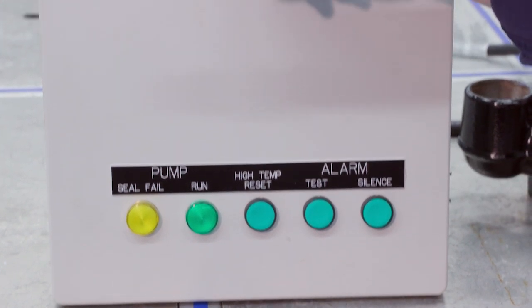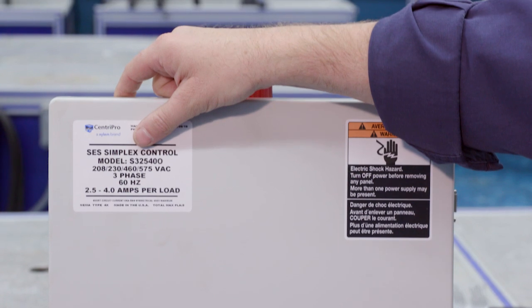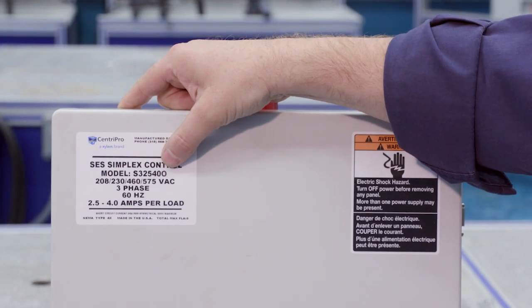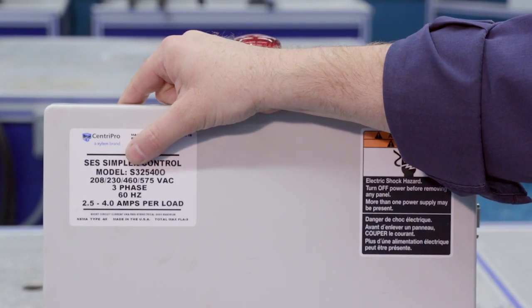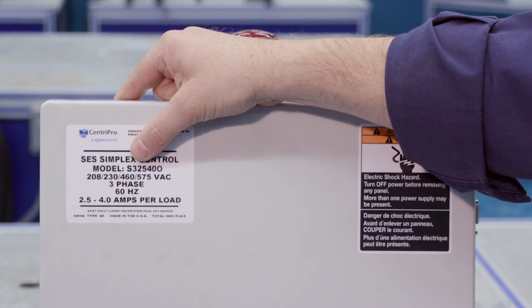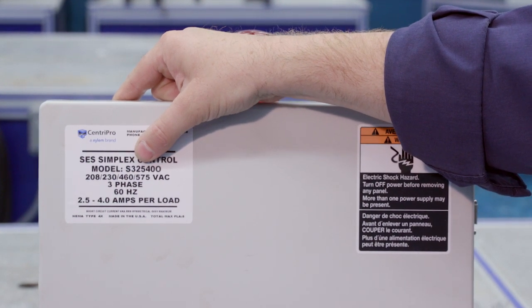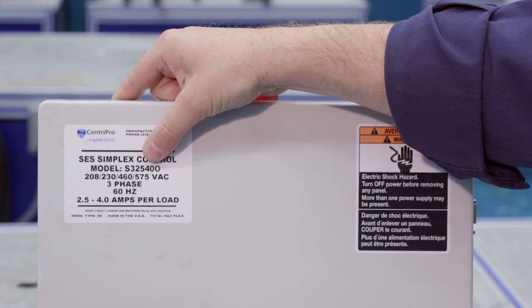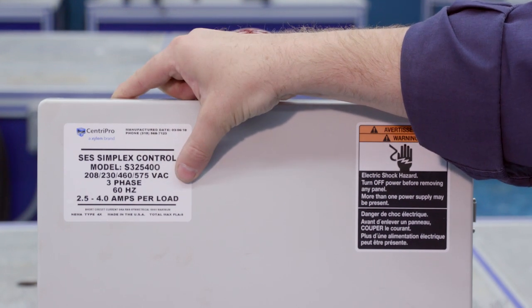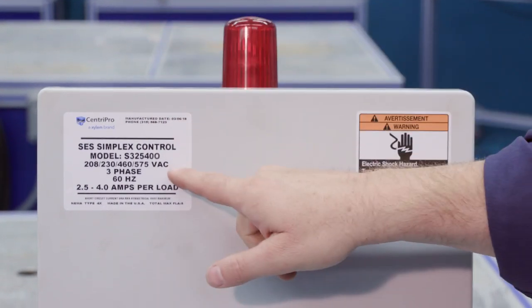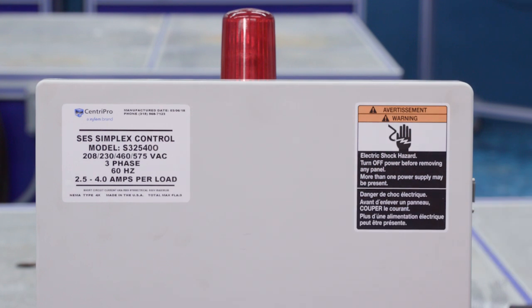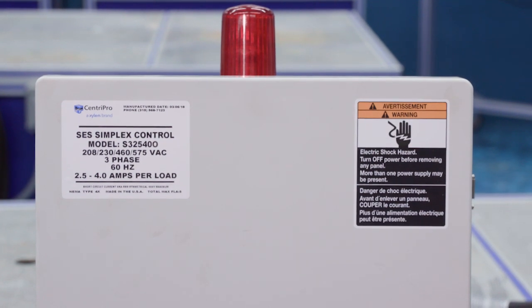As we move up to the nomenclature here, model S325400. That's a simplex, 3 for 3-phase, 2.5 to 4 amps, and again 3-phase. Important here is it's a multi-voltage panel: 208, 230, 460, 575, and we'll show how to make that setting inside the panel.